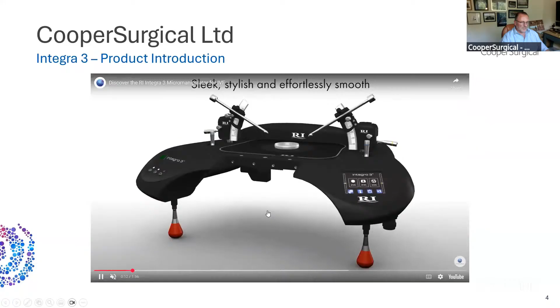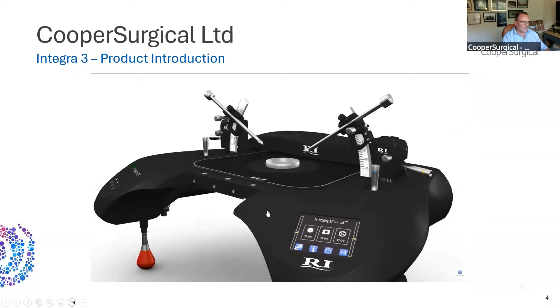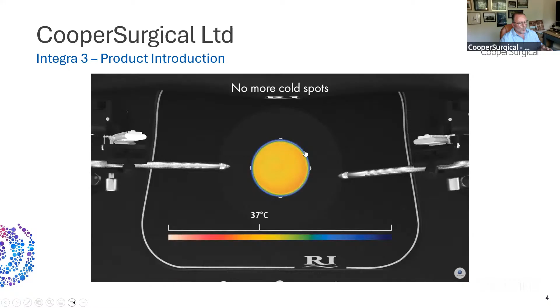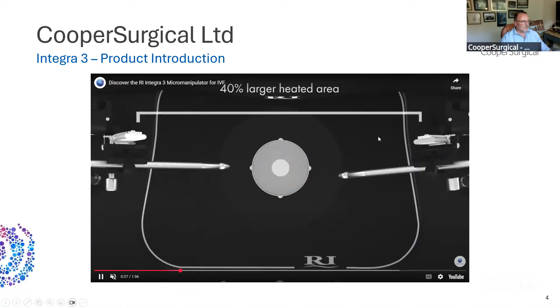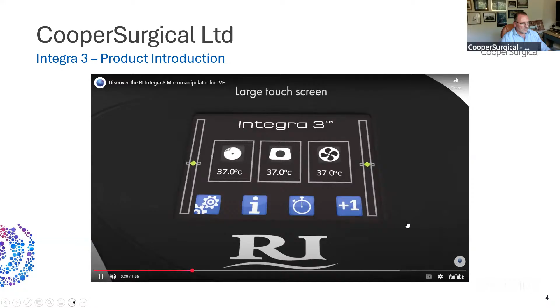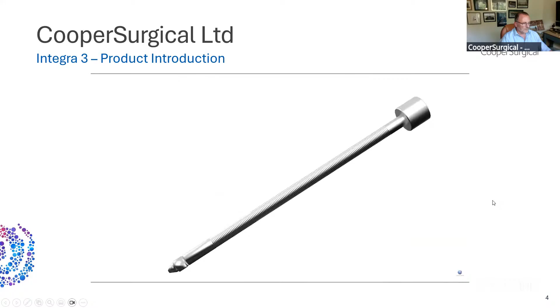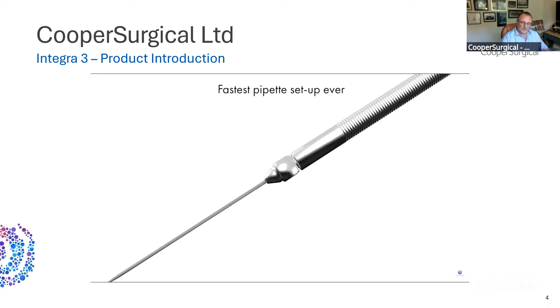So the Integra 3 micromanipulator is the most recognized micromanipulator system in fertility, and here is the instrument. It combines the manipulators, the XY stage, and the heating elements all in one design. The heated area incorporates a product called ThermoSafe, which is unique to Integra 3 and bathes the area in warm air, so you don't get any cold spots, so the objective doesn't draw any heat. There's also a very large heated area, which is controlled independently. So you've got 3 heated areas, the ThermoSafe and the 2 heated plates. We have a manipulator, which is a fast pipette setup. And exchange.